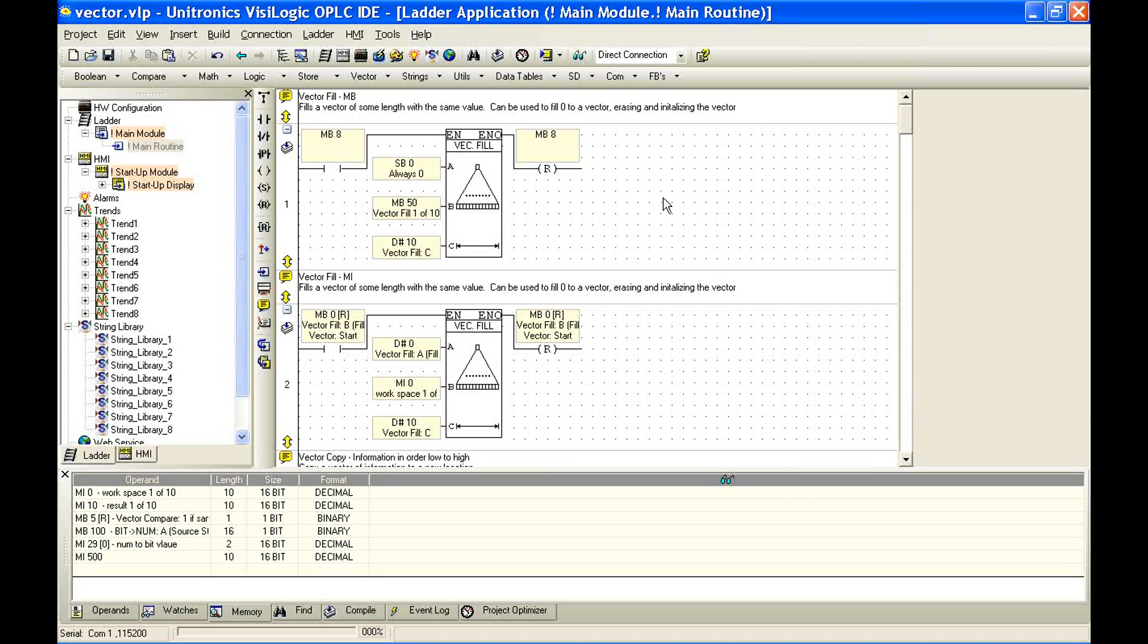We define a vector as a start address with some length. So if I say a vector at MI10 with length 5, I'm specifically talking about memory integer 10, 11, 12, 13, and 14. Now we have a number of tools that help us work with vectors. But let's talk again about what is a vector. A vector is a collection of information. Instead of having five integers randomly strewn about the controller, we've organized our information into five pieces of information in a row.